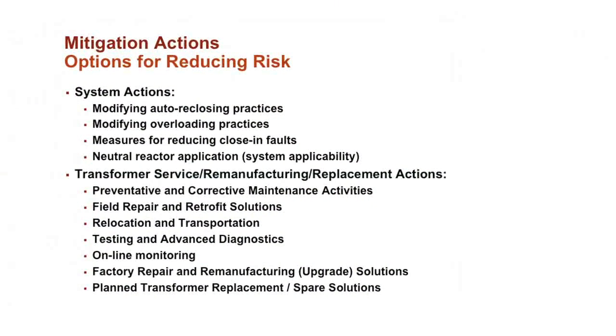This is an example of a smaller fleet study for just one particular site. So in this case, there were only 11 transformers, and a risk of failure was calculated for all of them. For this one, a design study was not done. It was done more based on the condition of the transformers and what was known about their design. So I just want to show it can be done for a large fleet, for a smaller fleet, or just for one location.